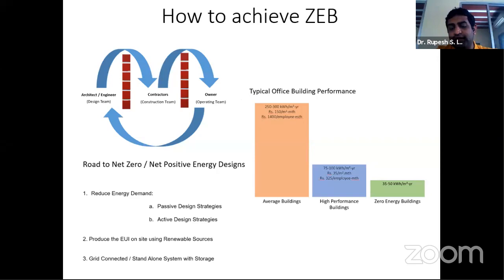Zero energy buildings, the benchmark is a little higher. So the EUI, or the energy utilization index, in the zero energy buildings case would be somewhere around 35 to 50 kilowatt hour per meter square per year. So this shows what the benchmarks are, or when we design a building, what kind of benchmark of energy we are trying to achieve. So based on that, the design considerations could be put into place.